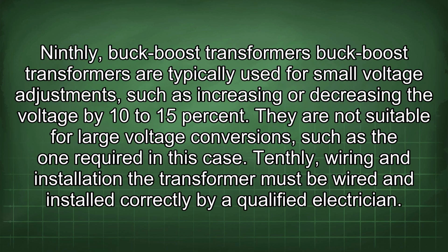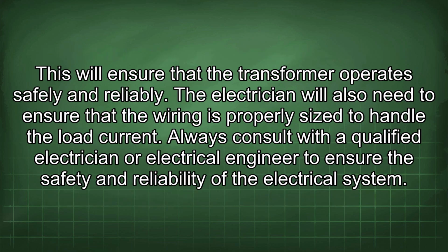Ninthly, buck-boost transformers. Buck-boost transformers are typically used for small voltage adjustments, such as increasing or decreasing the voltage by 10 to 15%. They are not suitable for large voltage conversions, such as the one required in this case. Tenthly, wiring and installation. The transformer must be wired and installed correctly by a qualified electrician. This will ensure that the transformer operates safely and reliably. The electrician will also need to ensure that the wiring is properly sized to handle the load current. Always consult with a qualified electrician or electrical engineer to ensure the safety and reliability of the electrical system.